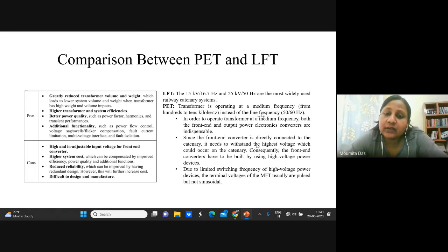Since the transformer can operate at medium frequency, the front end and the output power electronics converters are important in this case. If we are considering tens of kilohertz, let's say 50 kilohertz, then power electronics converter switches are required in order to process that power in that frequency range. So that is why it is very important here. But in a line frequency transformer, it is not that important to have power electronics converters.